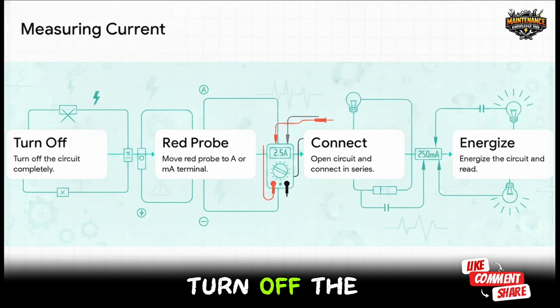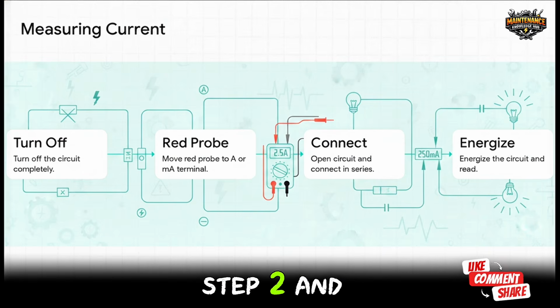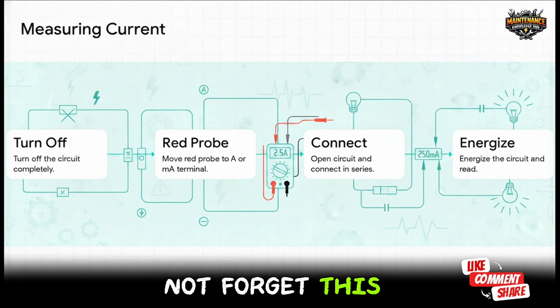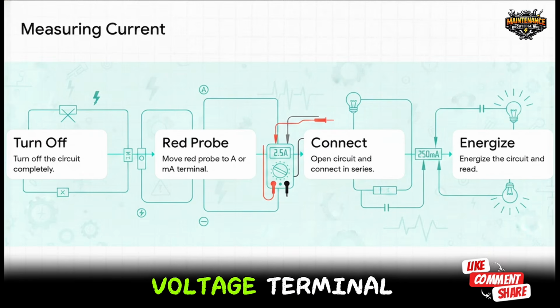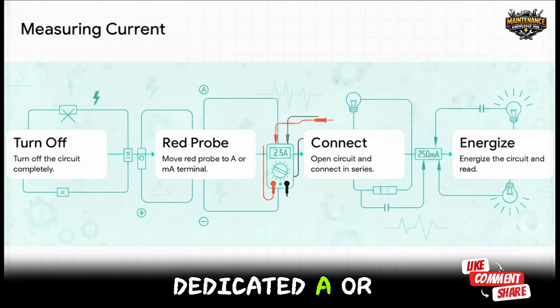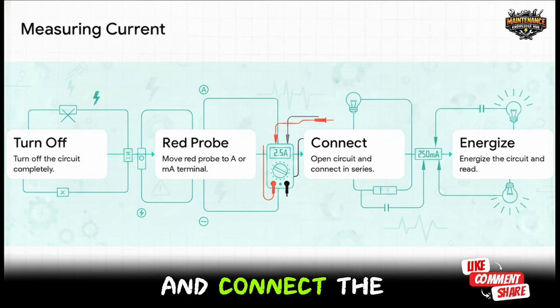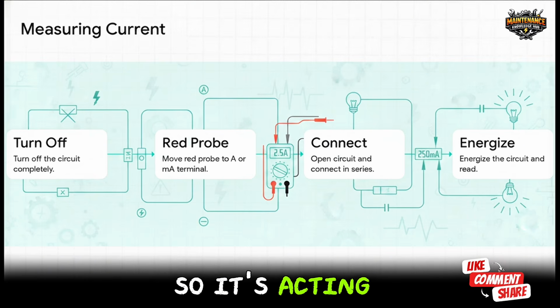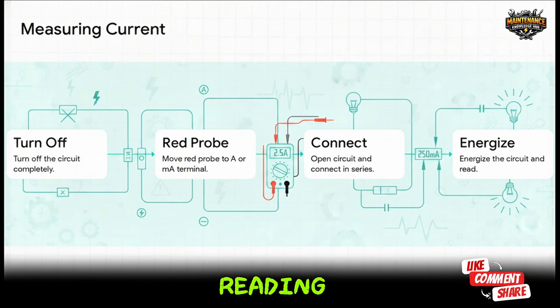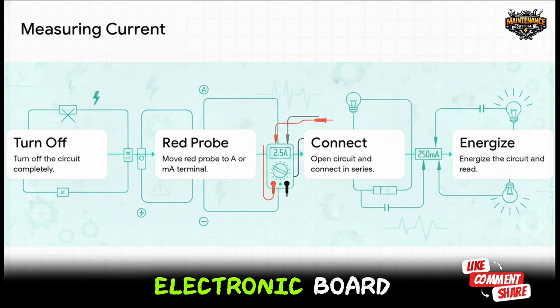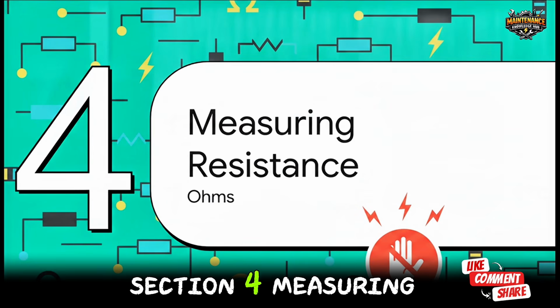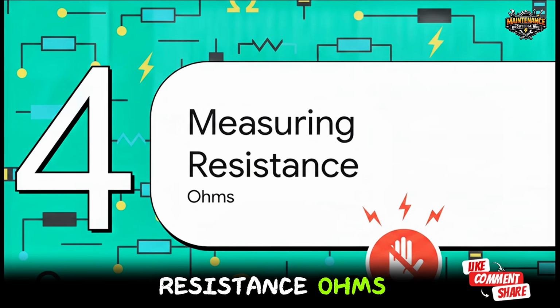Step 1, turn off the circuit entirely. Step 2, and you really must not forget this, move your red probe from that voltage terminal over to the dedicated A or mA terminal for current. Step 3, open the circuit and connect the multimeter in series so it's acting like a bridge. And step 4, energize the circuit and take your reading. This is exactly how you'd measure, say, a 2.5 amp motor control circuit or maybe a smaller 250 milliamp electronic board.